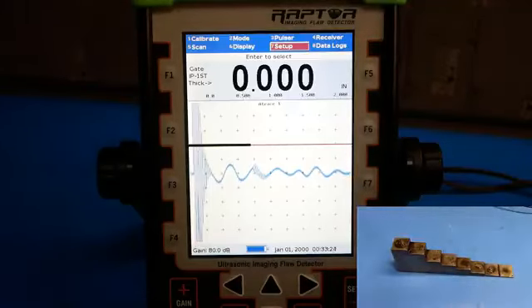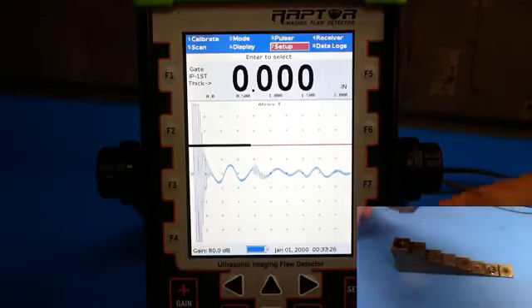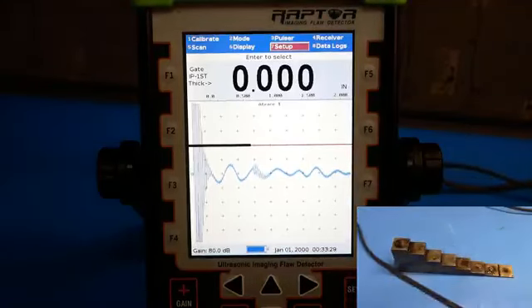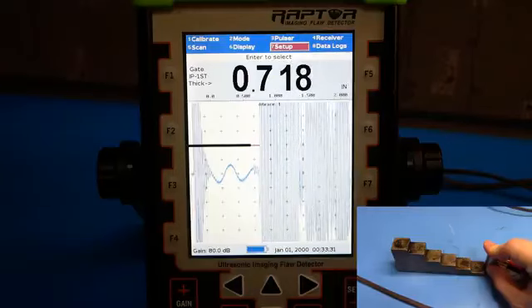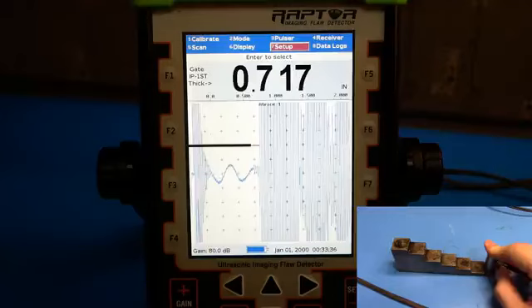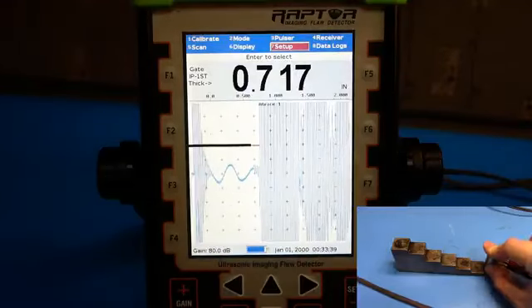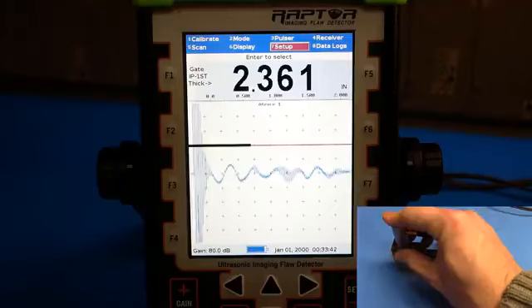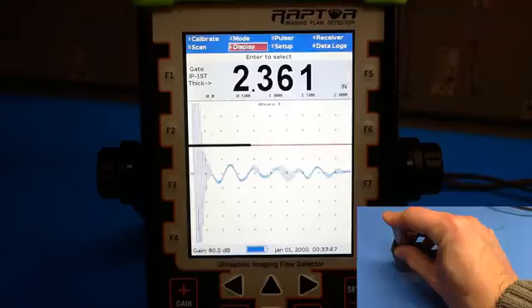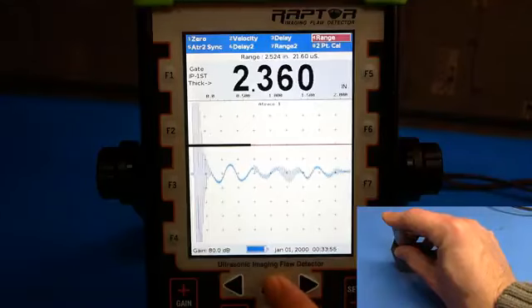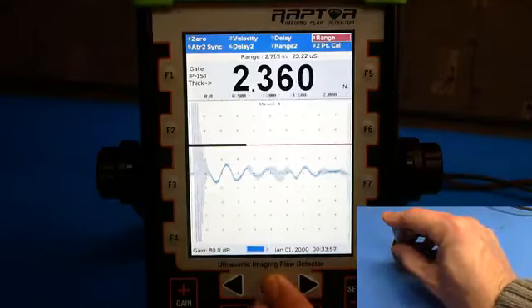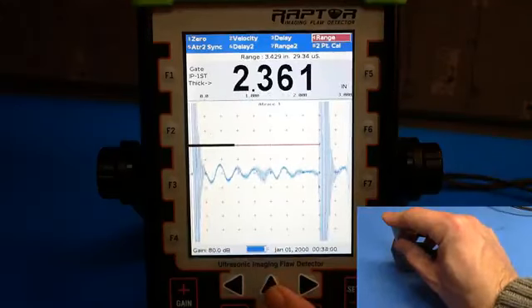We're going to select 1.75 inches for the upper bound and 0.1 inches for the lower bound. We'll want to do this to make sure that our range is set up correctly. Coupling to the 0.1 inch block, I can see a strong echo, but coupling to the 1.75 inch part of the block, I don't see any echo. To fix this, we'll go to calibrate, we'll go to range, and we'll use the up and down arrow keys to adjust the range until we see an echo from the top part of the step block.